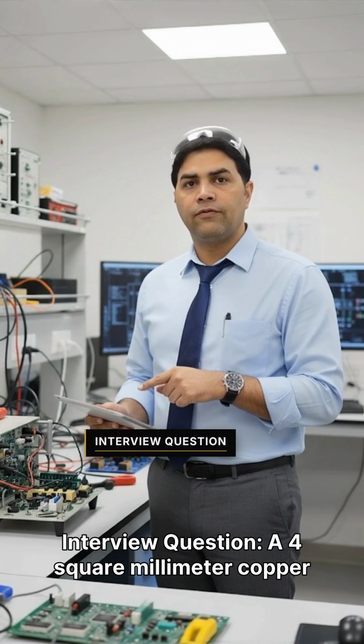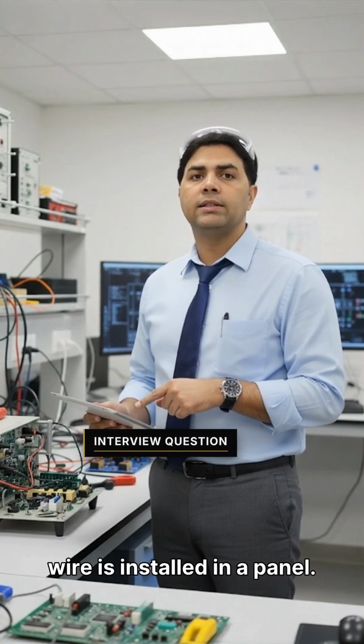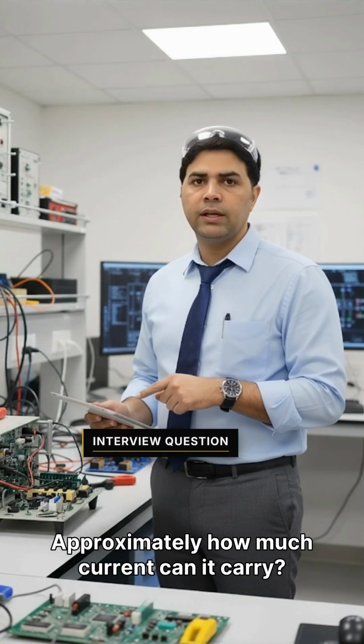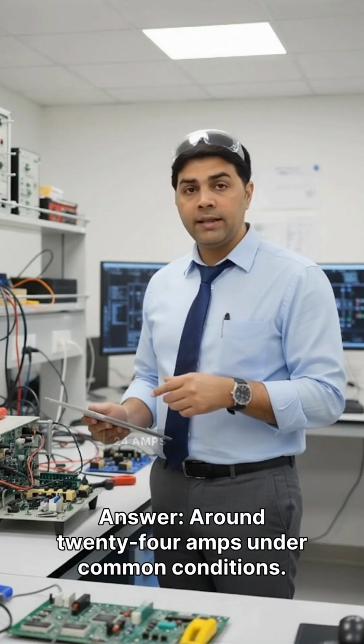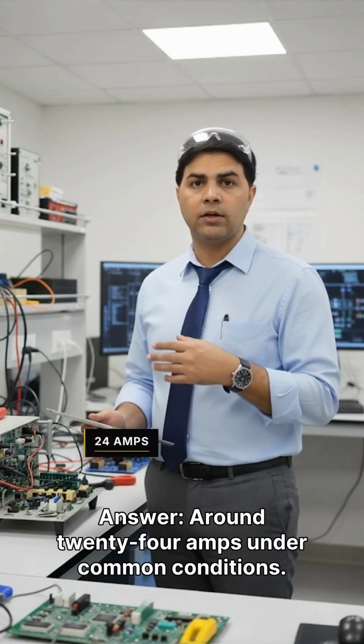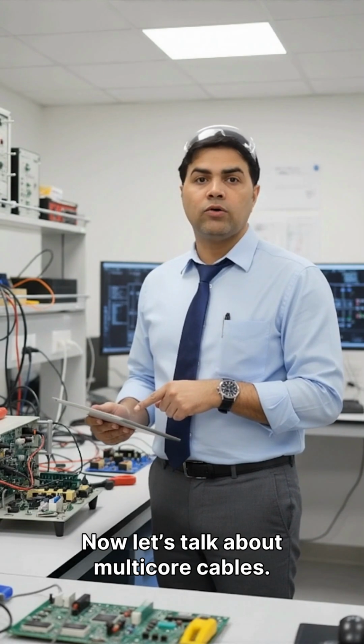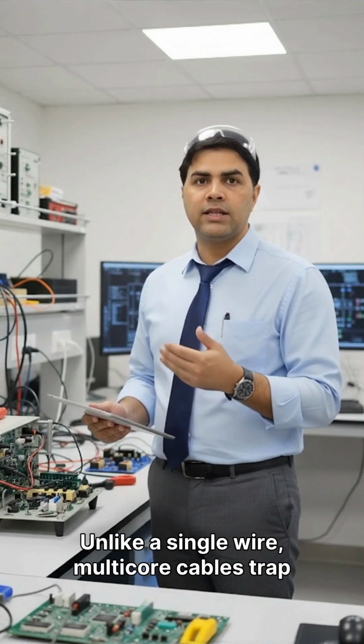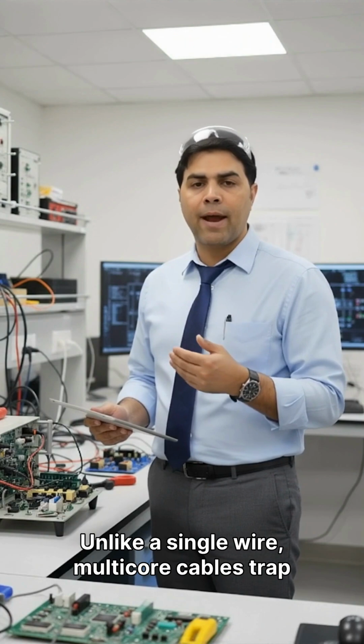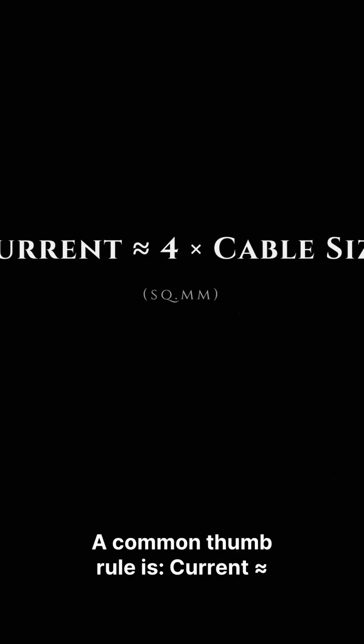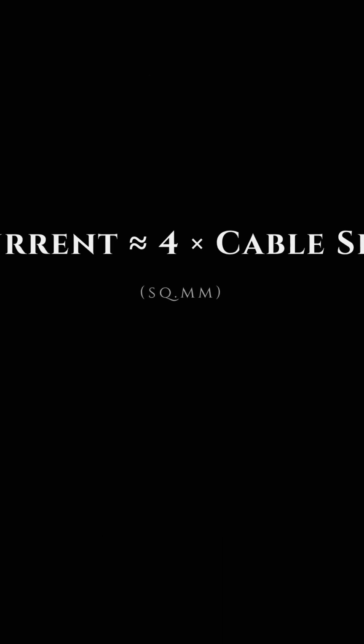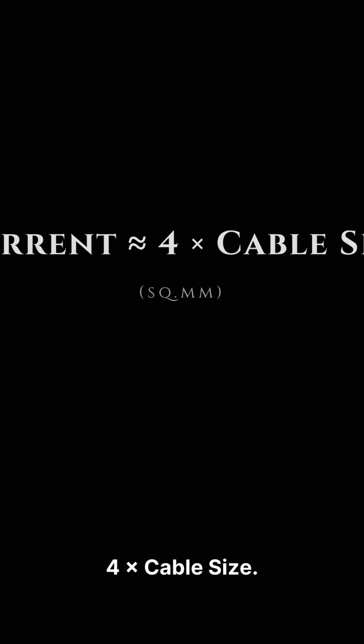Interview question: a 4 square millimeter copper wire is installed in a panel. Approximately how much current can it carry? Answer: around 24 amps under common conditions. Now let's talk about multi-core cables. Unlike a single wire, multi-core cables trap more heat. That means they usually carry less current. A common thumb rule is current approximately equals 4 times cable size.